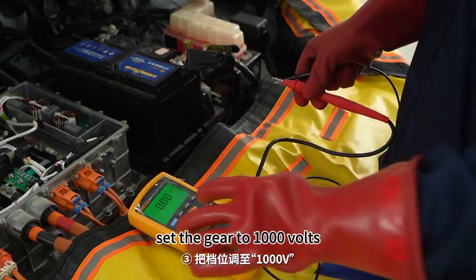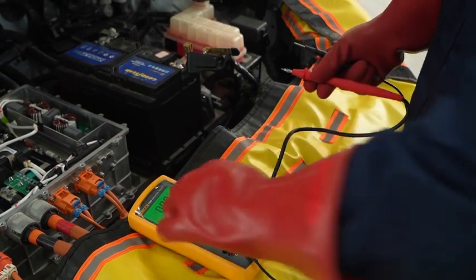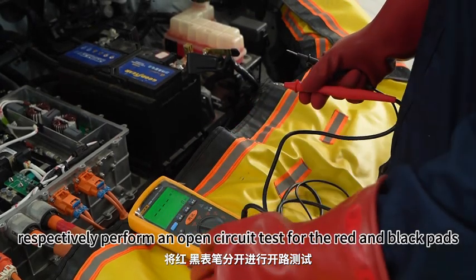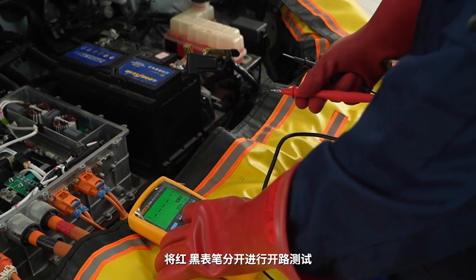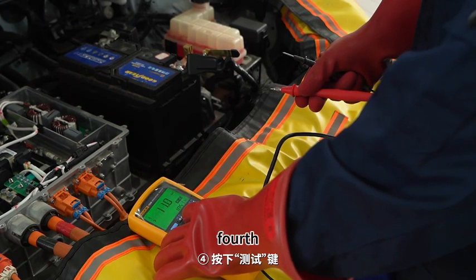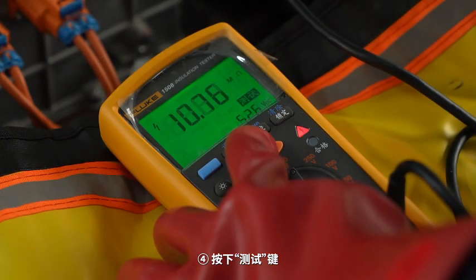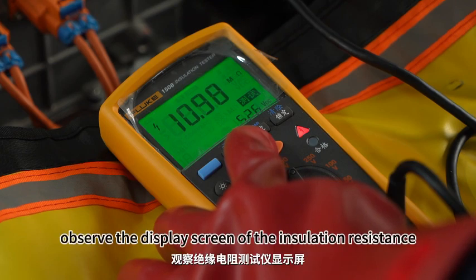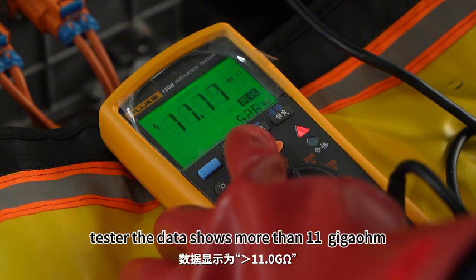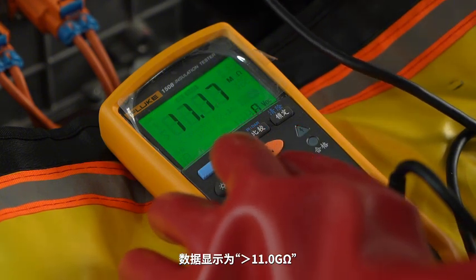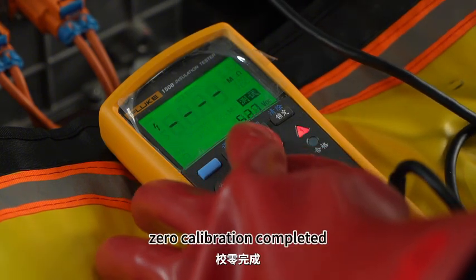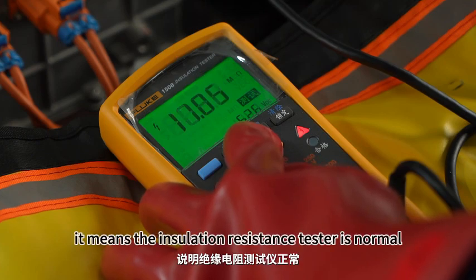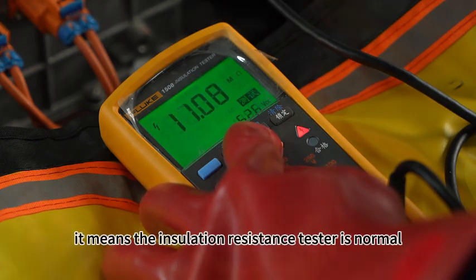Third, set the gear to 1000 volts. Perform an open circuit test with the red and black probes. Fourth, press the test button. Observe the display screen of the insulation resistance tester. The data shows more than 11 gigohms. Zero calibration completed. It means the insulation resistance tester is normal.